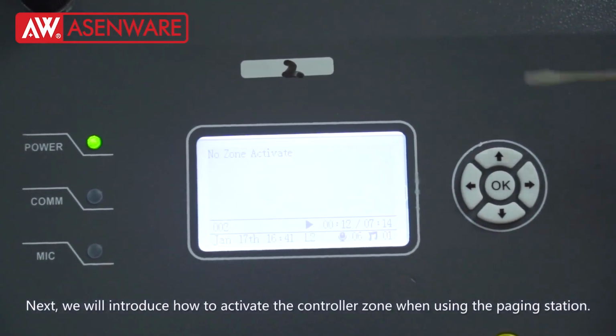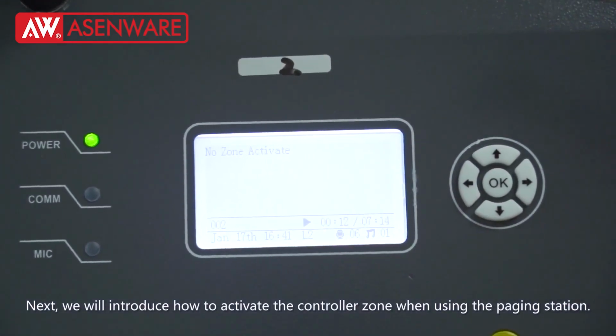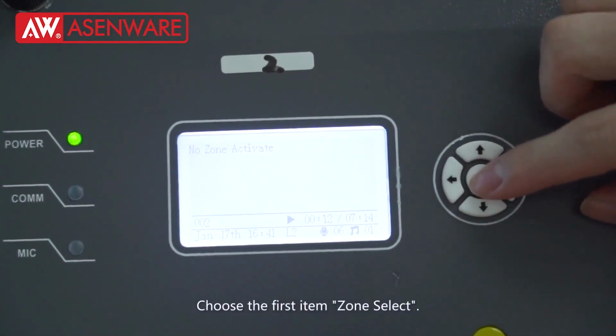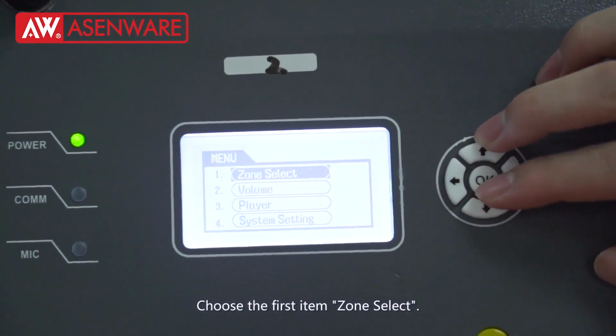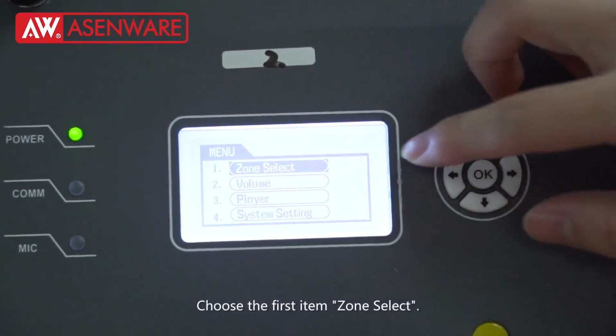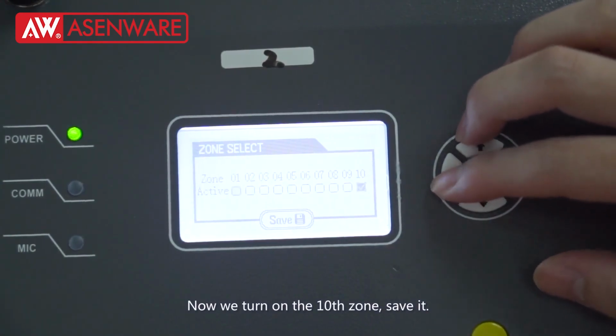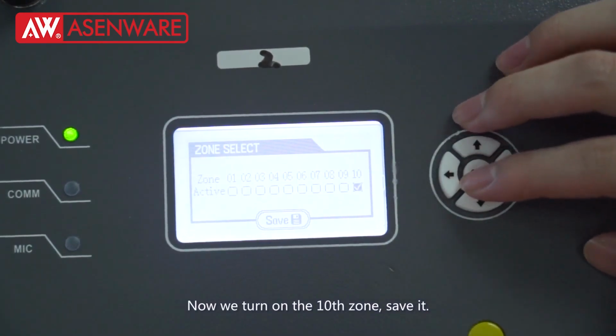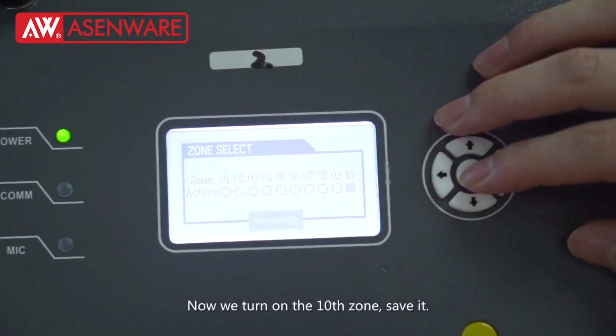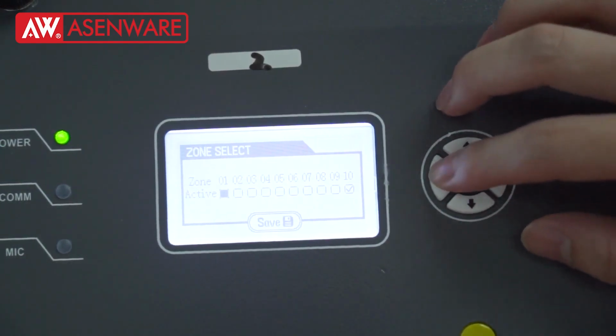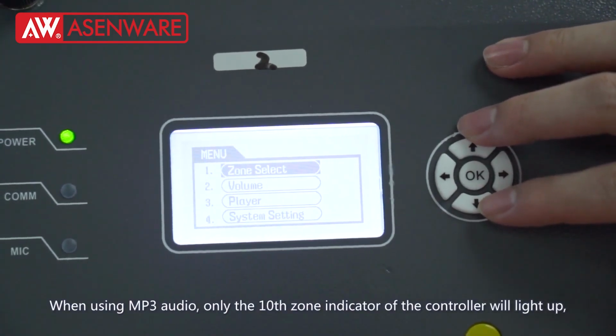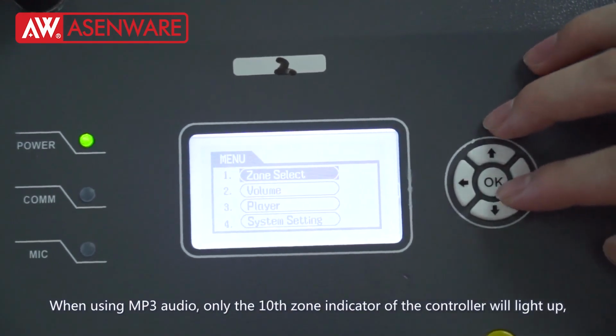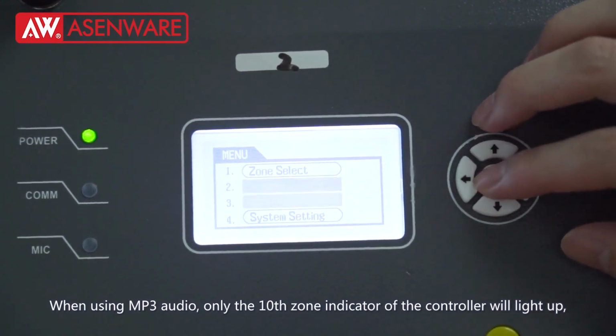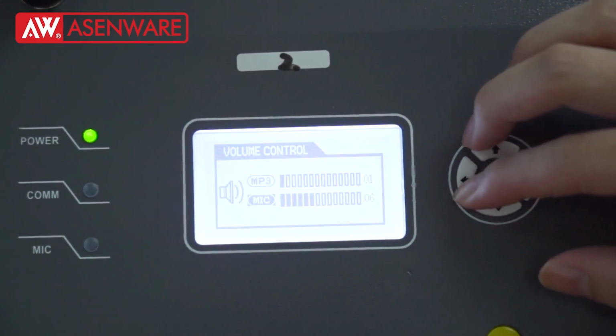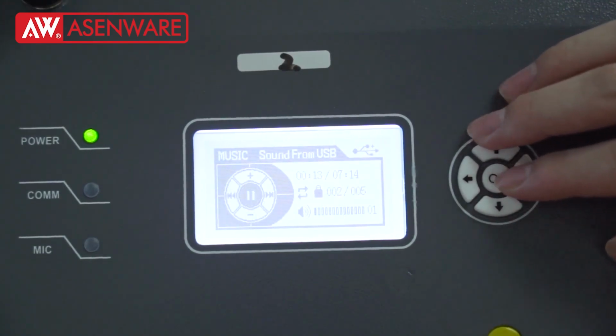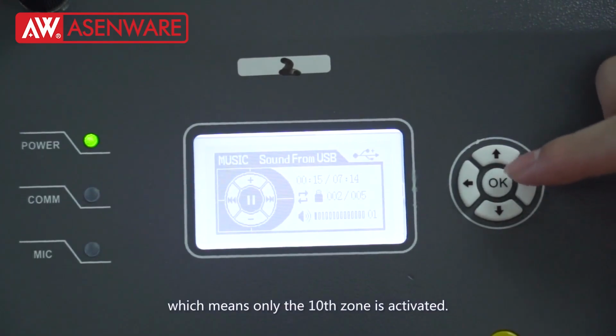Next, we will introduce how to activate the controller zone when using the paging station. Choose the first item, Zone Select. Now we turn on the 10th zone and save it. When using MP3 audio, only the 10th zone indicator of the controller will light up. Which means only the 10th zone is activated.